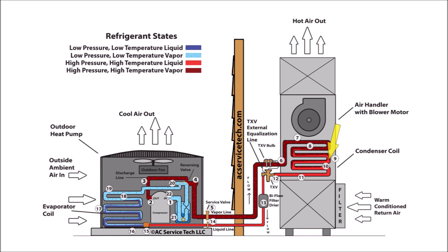Remember that any time the saturated refrigerant is rejecting heat, it's not going to be lowering in temperature. What is happening is that where it starts off near step eight, it's mainly a vapor and partially a liquid. But as it goes through the saturated state while it's rejecting heat over by step ten, right before that, it's mainly a liquid and just partially a vapor.